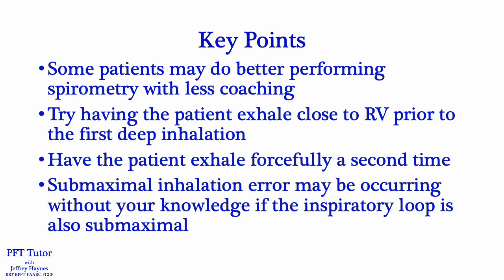Things you can do to try to correct the submaximal inhalation error: Try having the patient exhale first into residual volume just like you do with DLCO prior to that first deep inhalation. You can always have the patient do a second forced expiratory maneuver if the inspired volume is obviously deeper than the first one. A submaximal inhalation error may be occurring without your knowledge. The inspiratory loop is helpful at identifying, but as I showed a few slides ago, this can still be present if the inspiratory loop is submaximal.